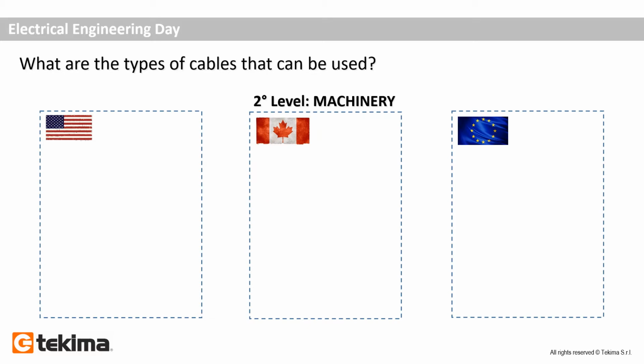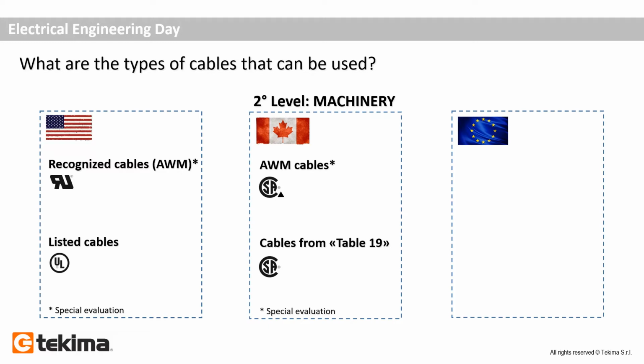For machinery in the USA, when I choose the wiring method, again I have to define which type of cable is needed. Two options in my pocket: AWM cable, recognized cable, and listed cable. So both are admitted in this case. It's mandatory to observe that AWM cables could be used for industrial machinery. We also have to consider the installation because of the standard. In fact, I will consider some special evaluation depending on the application. Same situation in Canada. Moreover, for the EU market, all the third-party certified cable is recognized as valid.